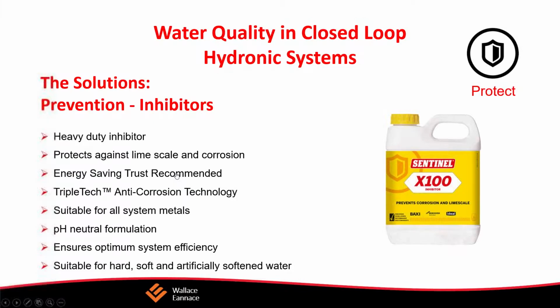So the system that we have, the Sentinel system, offers lifetime protection for hot water heating systems by cleaning, protecting, and maintaining the system. In older systems, we offer a product called X800. It quickly reduces deposits and scale in roughly an hour. It's a fast-acting cleaner with unrivaled chemical technology. It dissolves corrosive debris, can work in cold systems, and can also be used as a power flushing device.